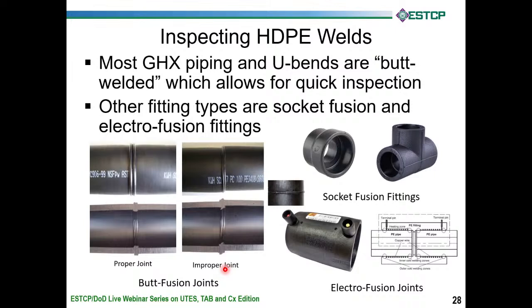So I'm going to start with the types of fittings that you have. The key thing with the HDPE pipe, in my opinion, is that you weld it. There are some systems that are at higher temperature, and you have to use PEX on that, or if some of you saw the UTES seminar we did last month, which is high temperature storage between 250 and maybe 500 degrees Fahrenheit for high temp thermal storage purposes, or even electrical production, then you have to go to metal tubing. But the vast majority of all geothermal heat pump systems are constructed of high density polyethylene.